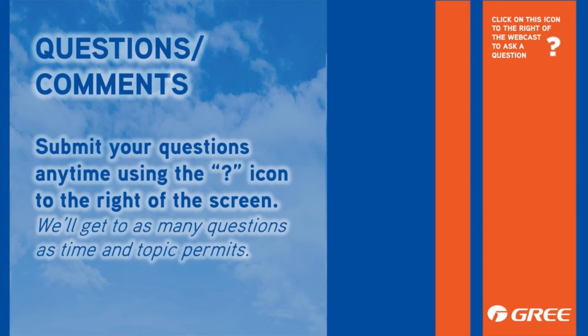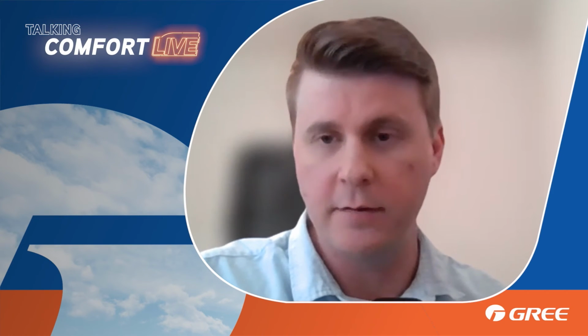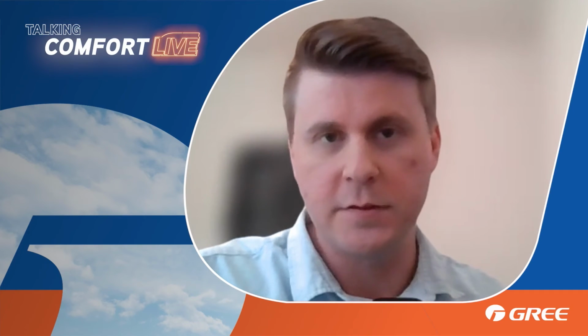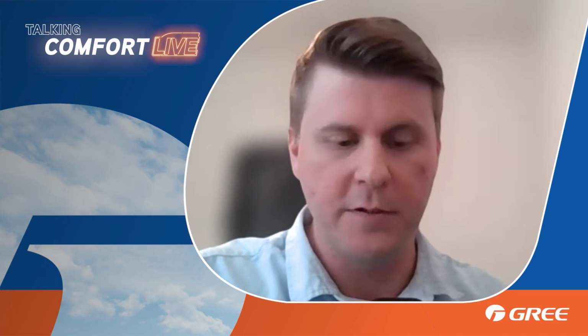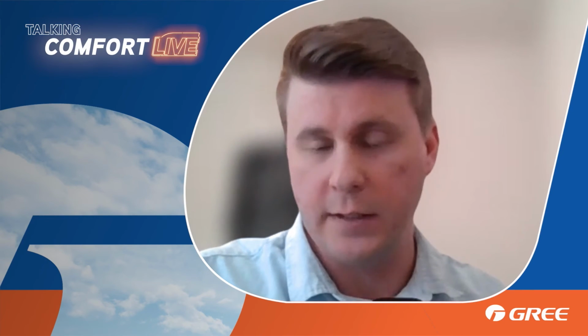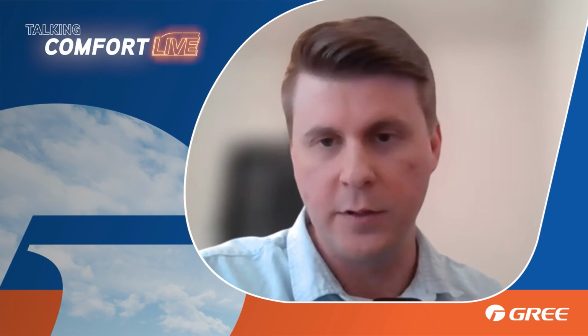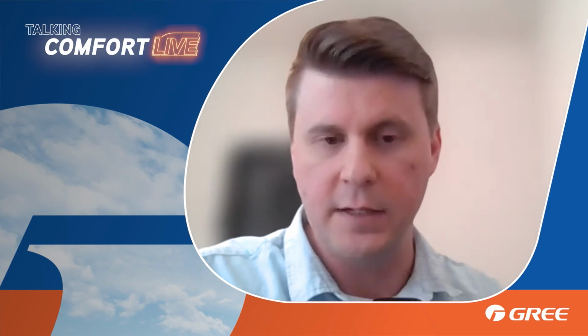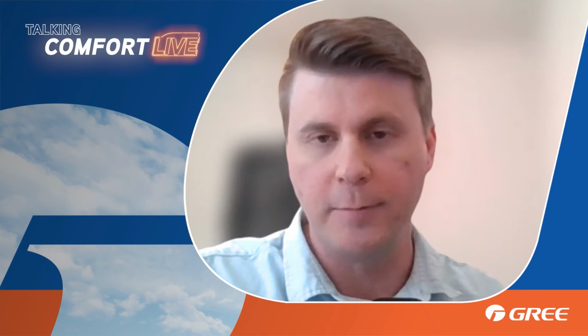So Justin, I'm going to give this one to you. Can we use the Flex condensing unit to match existing other manufacturer air handlers? Yes, you can. In fact, there are other manufacturers out there such as ADP and Aspen who create 24-volt controlled R410A air handlers that are actually rated, and if you go on AHRI you can find those ratings. With other major manufacturers like Trane or Carrier, you won't find AHRI ratings. That said, as long as the indoor unit is 24-volt controlled, R410A for the time being, and has a TXV, you can pair it with the Flex outdoor unit and it will run.